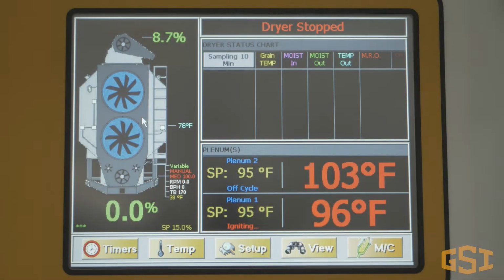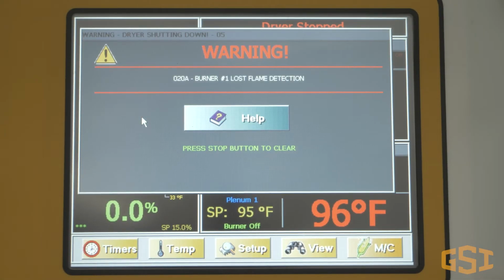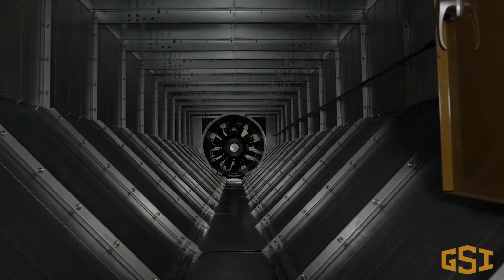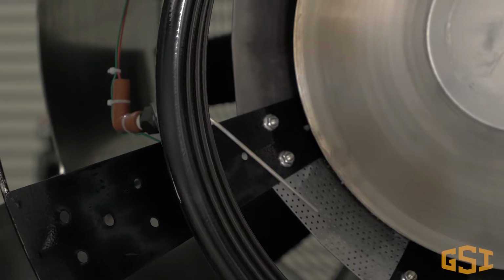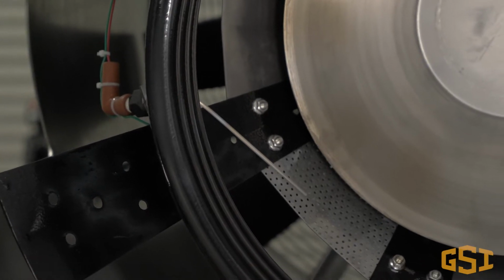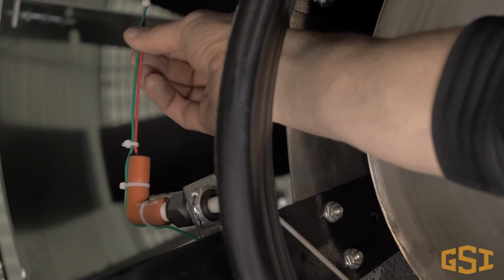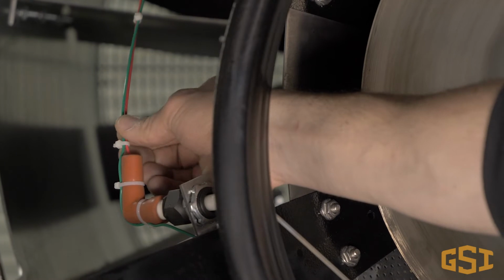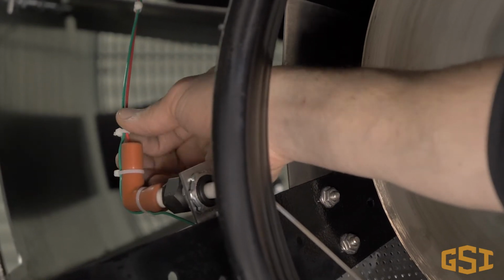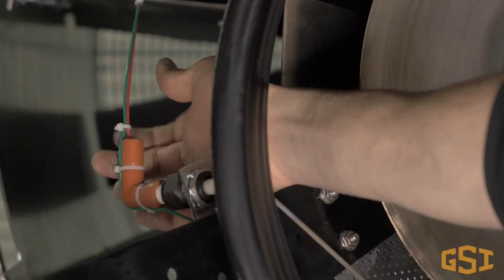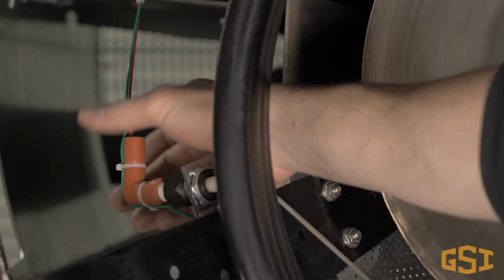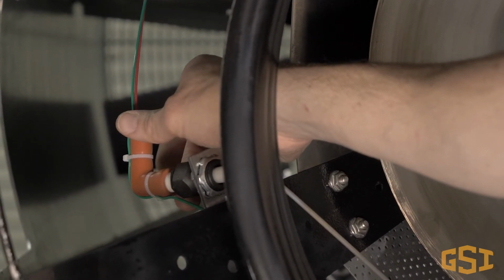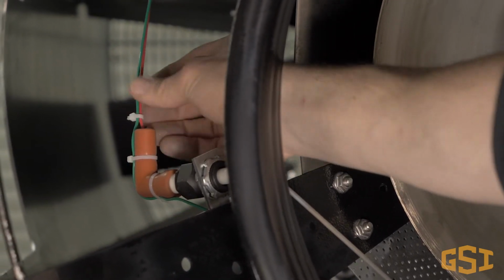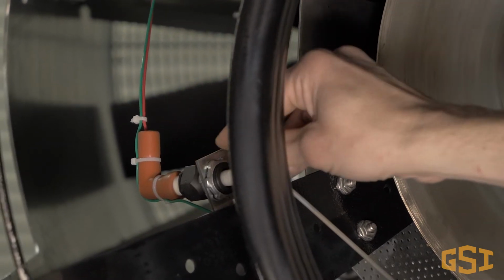How do you resolve a loss of flame error? Before we get into the more advanced troubleshooting techniques, let's check out the obvious things that can cause a loss of flame error. Check the high temperature wire attached to the top of the flame probe. Ensure this is a tight connection and the wire inside the connector is secure. If there is a break in this wire, you have an open circuit and flame detection is impossible.